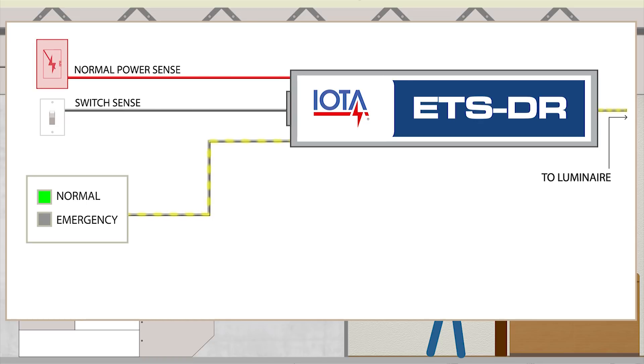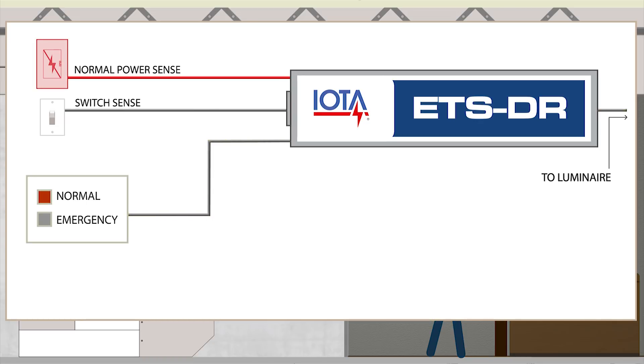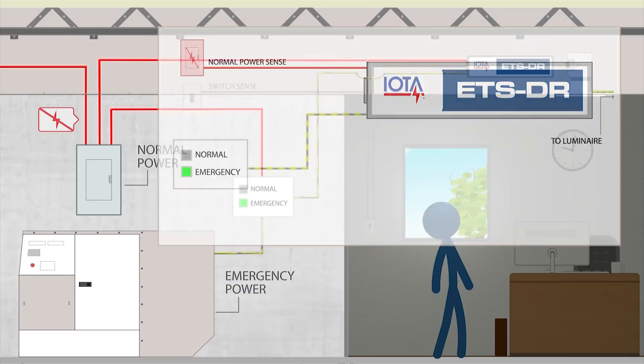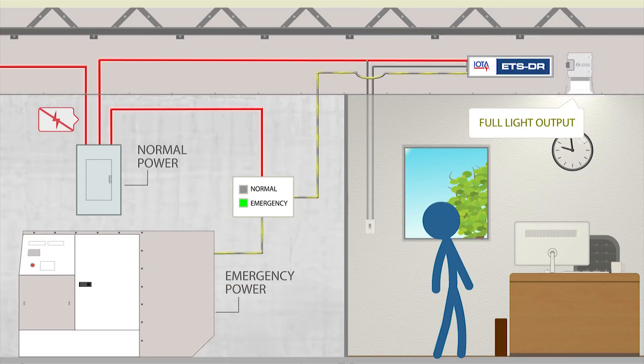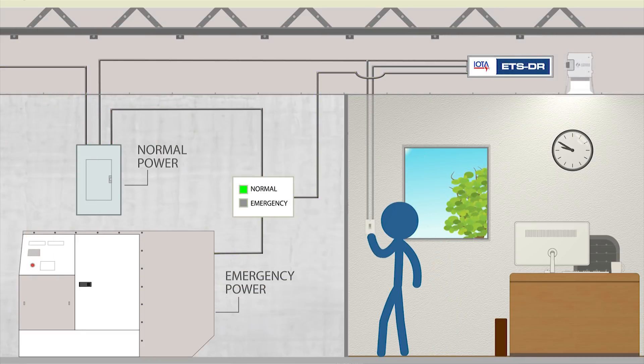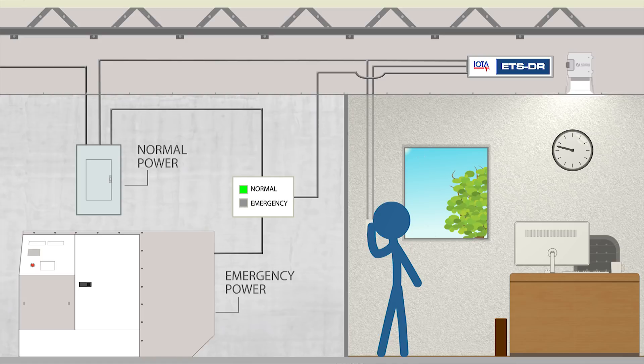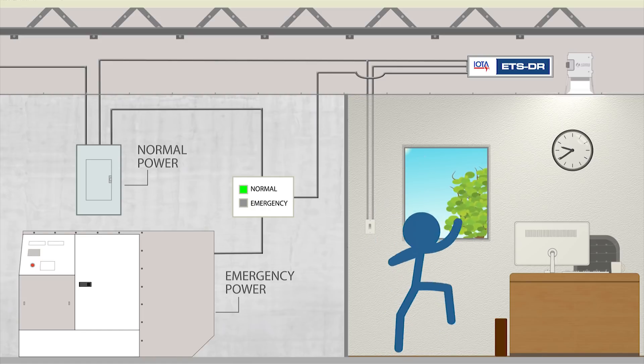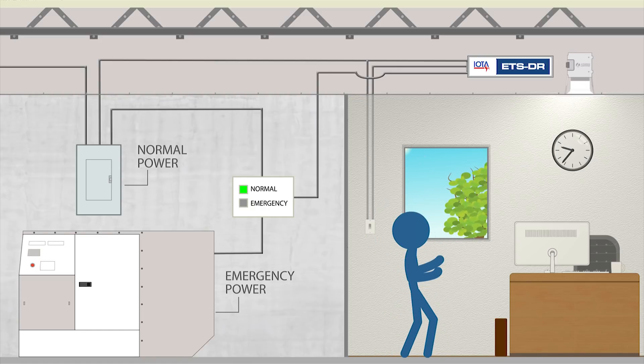the ETSDR detects the drop in normal power and begins to ignore the position of the switch, allowing power to reach your luminaires at full light output. This allows you to benefit from the increased control and potential energy savings of using control devices on both normal and emergency fixtures.